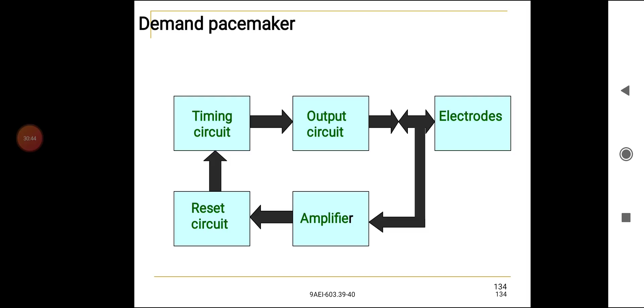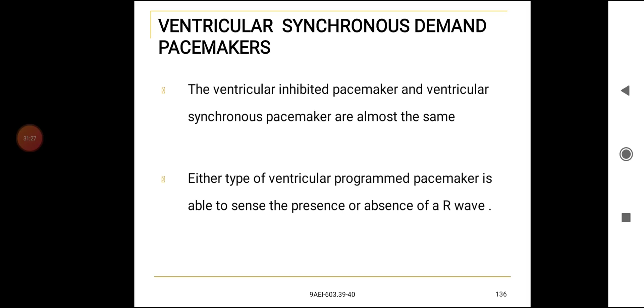Ventricular synchronous demand pacemakers. The ventricular inhibited pacemaker and ventricular synchronous pacemakers are almost the same. Either type of the ventricular programmed pacemaker is able to sense presence or absence of R wave. In the case of demand pacemaker, the output of the pacemaker is suppressed as long as the R wave is present.